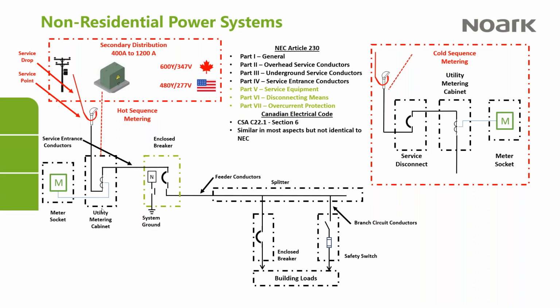The owner of the building must supply this though, okay? Then the utility comes along and they'll put a meter in a meter socket that's connected to the secondary side of these transformers. The meter base must also be supplied by the building owner. Then the power moves from there into the service entrance disconnect. I'll talk a lot more about what a disconnect is and what that means. But this is where that system ground comes into play. And what you'll see is that I've shown a link here in the connection.